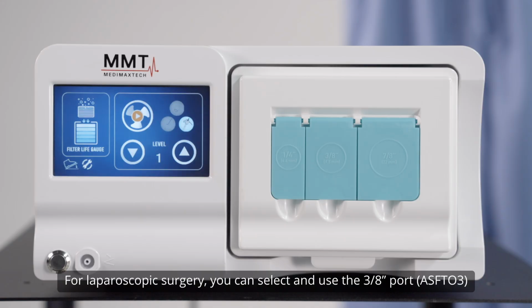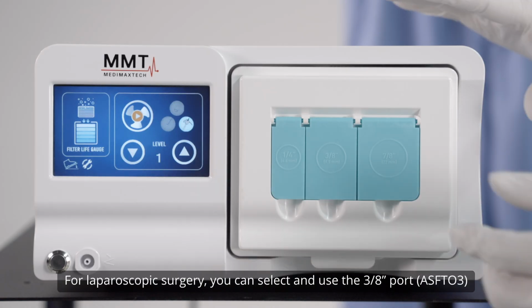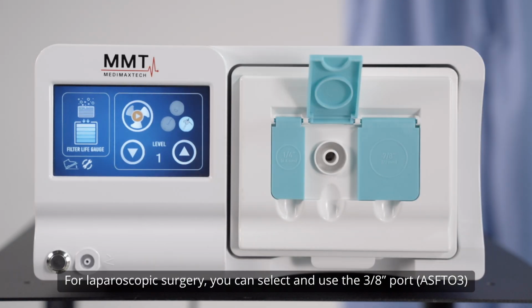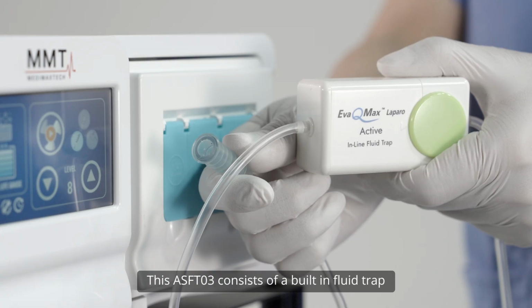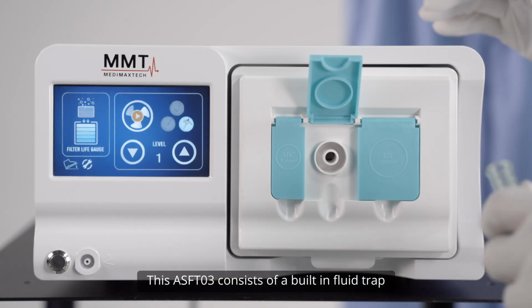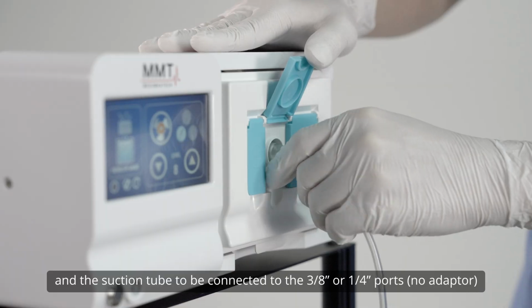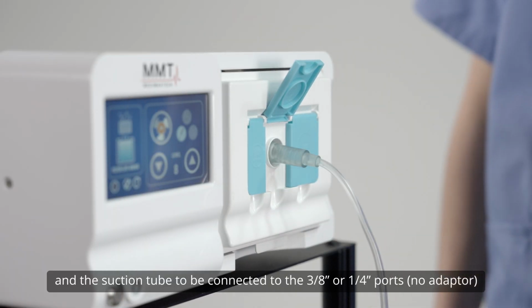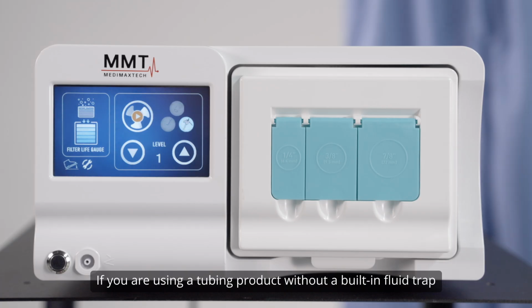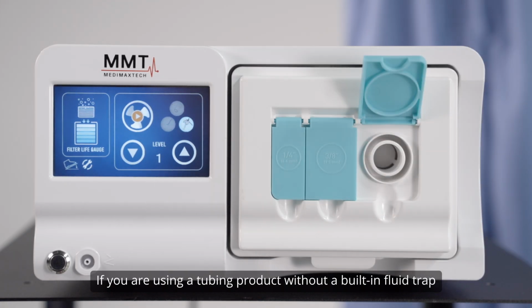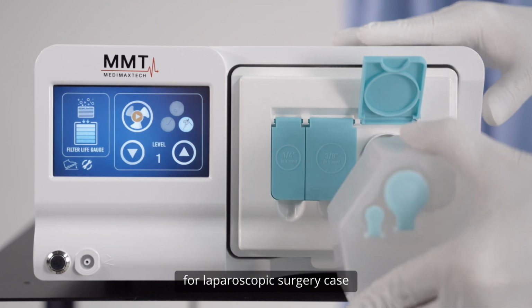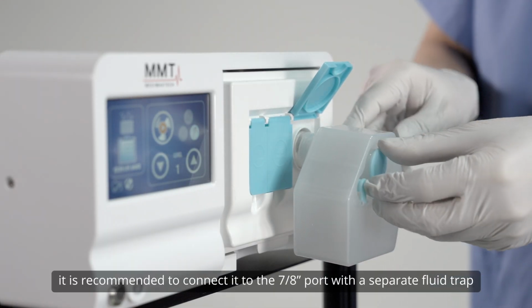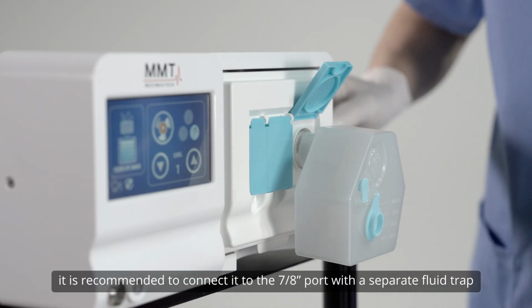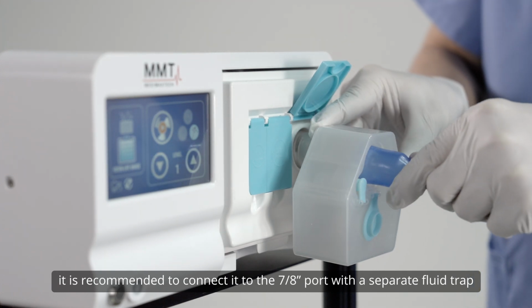For laparoscopic surgery, you can select and use the 3/8 inches port. This ASFTO3 consists of a built-in fluid trap and a suction tube to be connected to the 3/8 inches or 1/4 inch ports. If you are using a tubing product without a built-in fluid trap for laparoscopic surgery case, it is recommended to connect it to the 7/8 inches port with a separate fluid trap.